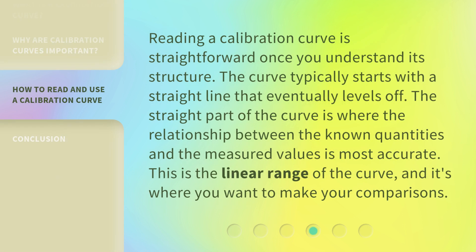A calibration curve is straightforward once you understand its structure. The curve typically starts with a straight line that eventually levels off. The straight part of the curve is where the relationship between the known quantities and the measured values is most accurate. This is the linear range of the curve, and it's where you want to make your comparisons.